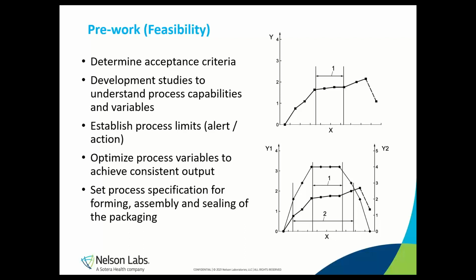The sealing specifications are the combination of temperature, dwell time, and pressure, which will be used for sealing. This includes the high and low for the range and the nominal settings, which will be used for production. These specifications will be proven and validated later, but during the pre-work or design phase of the validation, these details should be narrowed down to what will be validated.